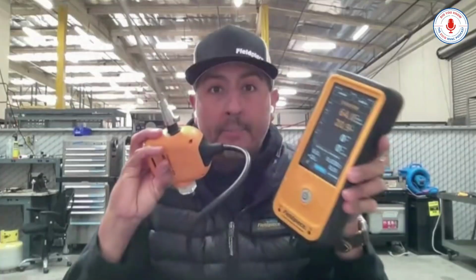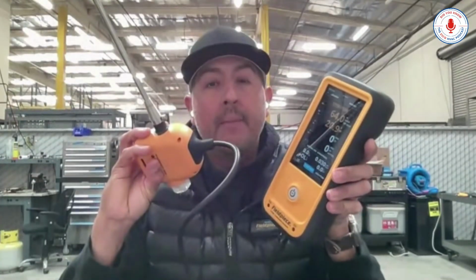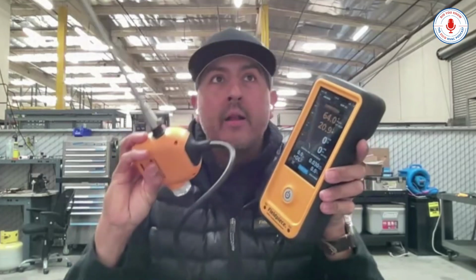Okay. Now, step two, walk into the building, right? What is very important is to perform an ambient carbon monoxide test as you walk through the building. Now, I've seen some contractors that I would call kind of alarming or concerning their customers. Like, hey, I'm walking through, checking to make sure there's no CO, making sure you guys are safe and not in danger. But there's a much more subtle way to just check for ambient CO, and you can use a combustion analyzer to help you do that.